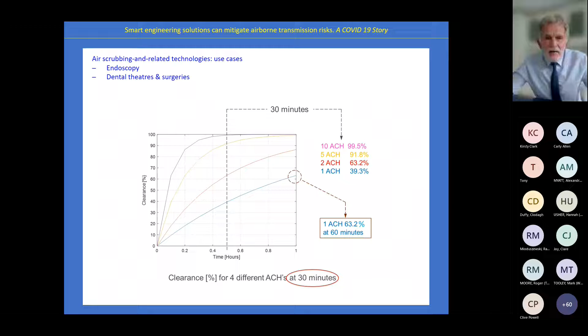How do we increase ACH? Well, upspec the building HVAC, the heating, ventilation, air conditioning system. Look in the ceiling where you're at the moment, you probably see grills like this, which may be admitting or removing air, and they're powered by big pieces of kit like this sitting on the roof of the building by and large. Very expensive. Something like 12% of the capital cost of building a hospital relates to the ventilation. In fact, with the new standards, probably even more. So what do we do? Replace, that's not economically viable.